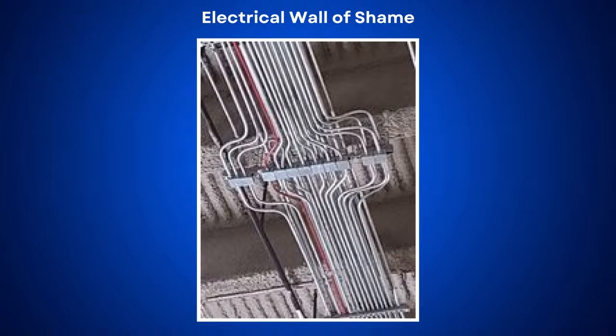I mean, everyone's like, oh, well, there's a fire alarm. It's like the fire alarm doesn't have to be on the same level. You could make the fire alarm go higher and then just offset when it gets to the gutter or the wireway or whatever. But it looks like some of the boxes below are blocking the other boxes above them.